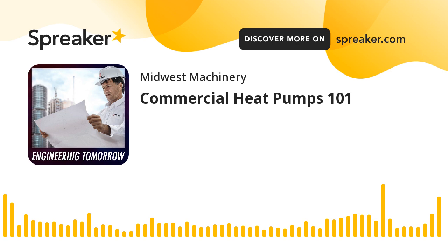But you also have that condenser fan outside that you're hearing. So that's a motor that's very loud. But that being said, the compressor does make noise. So I think most manufacturers of water source heat pumps do some things with the compressor. They put some isolation underneath the supports of the compressor to keep the vibrations down. Most manufacturers also offer an ultra quiet option, and that consists of double-walled insulation around the compressor compartment, and also putting some sort of sound blanket over the compressor itself. So most manufacturers nowadays have gotten pretty good at isolating that sound, so you don't even notice it.